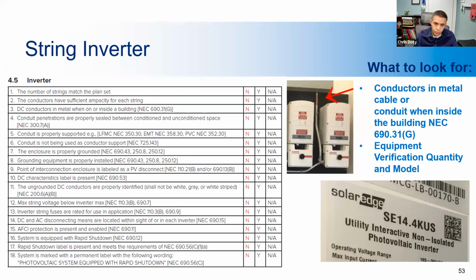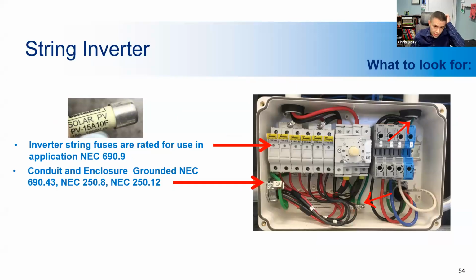So that's an important part. Here we have a look at the conduit bonding that's crucial to a safe installation. This conduit is bonded to the grounding wire and the grounding lug, so that the whole system is grounded. This has a non-metallic enclosure, which is why the conduit has to be grounded separately.